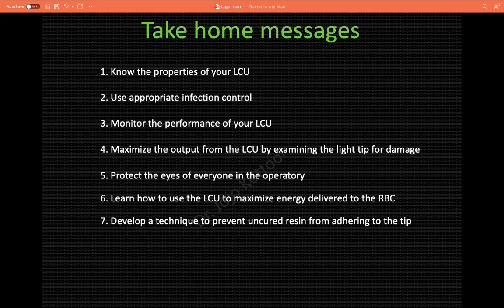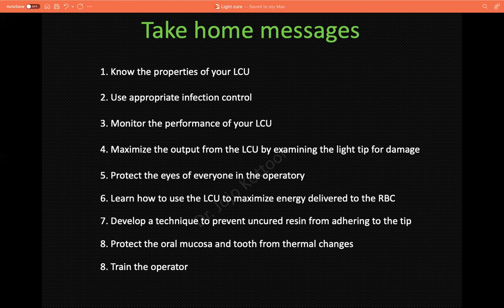To summarize the take-home messages: know the properties of your light cure unit — which unit you're using, its tip diameter, milliwattage, beam homogeneity, whether it scatters light. Use appropriate infection control — highly recommend barriers. Monitor your light cure unit with a radiometer at regular intervals. Maximize output by examining the light tip for damage and replacing if needed. Protect the eyes of everyone in the operatory. Learn how to use the light cure unit to maximize energy delivered to resin-based composites. Develop a technique to prevent uncured resin from adhering to the tip. Protect oral mucosa and tooth from thermal changes — don't cure continuously at high intensity. And most importantly: train your operator so all the good work doesn't fail.